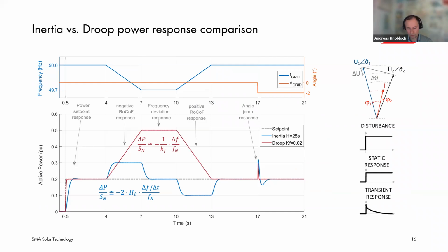So with our solution, we provide different types of responses to, let's say, grid events, or different control modes. We call them the inertia control mode and the droop control mode. And I would like to explain the difference based on this diagram here. So we have on the upper side the frequency, as a grid quantity or grid disturbance that is constant first, and then it is changed with a constant rate of change of frequency and some deviation.